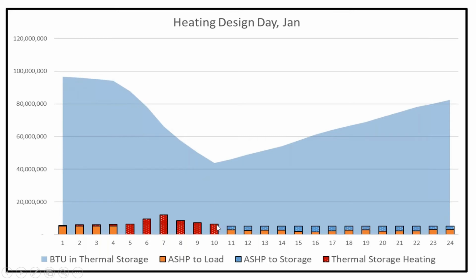And even after the design period on design day, the 6 coldest hours of the day on design day, we still have about half our storage left over, which we could use again the next day, even if we didn't rebuild the way we did. So there's a lot of energy storage at the building, and the energy's in the building, right next to surface area that is clean and undisturbed, right? So it doesn't matter what the outside temperatures are. It doesn't matter if it's snowing. It doesn't matter if coils are frosting up. You've already got this water in the tank ready to go and ready to be converted into energy at a usable level.